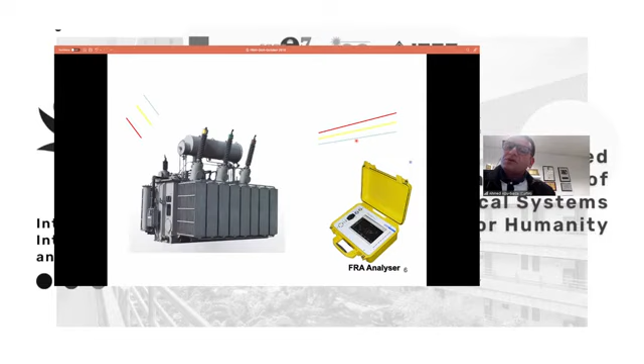And then you scan each phase of the transformer, phase A, phase B, phase C, with this small device. The device is called a frequency response analyzer, which injects a very low voltage, 10 volts only. But the voltage here is of variable frequency from 10 hertz to 2 megahertz. And you measure the impedance, or admittance, or the transfer function of each phase against the frequency. That's called the frequency spectrum or characteristic of each phase.